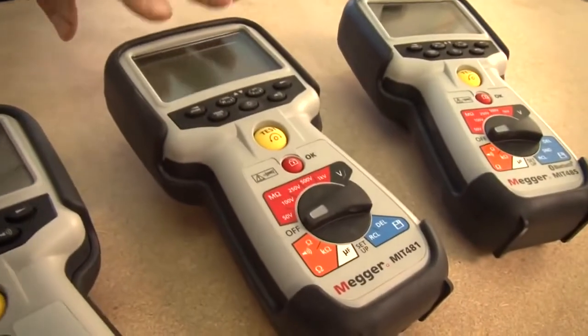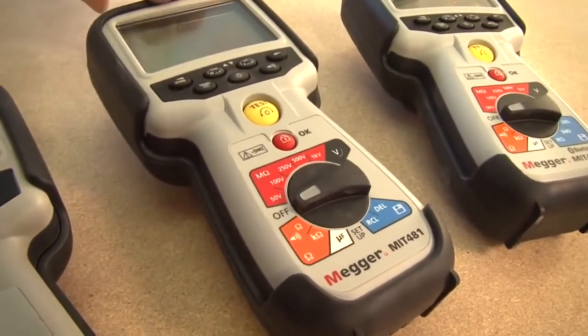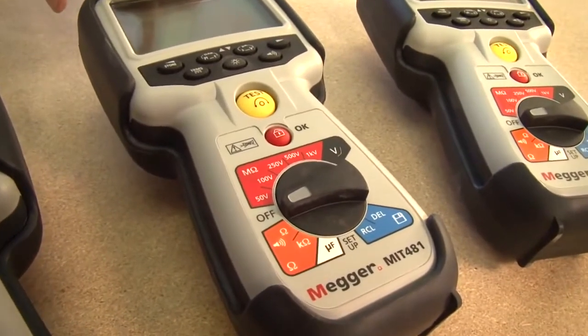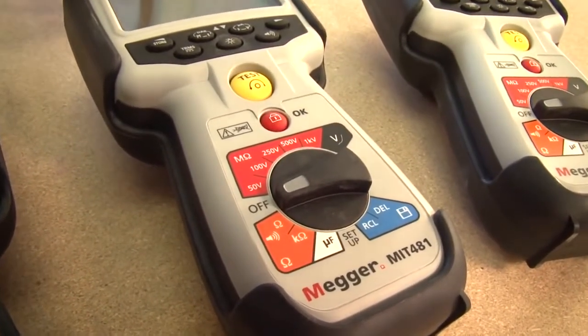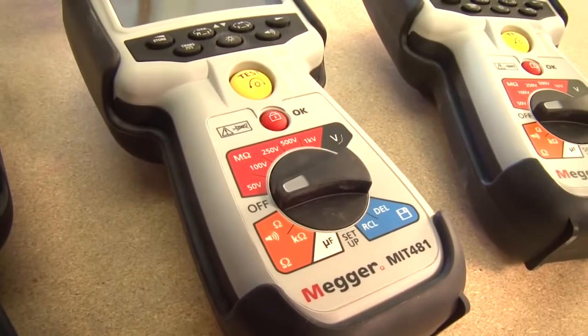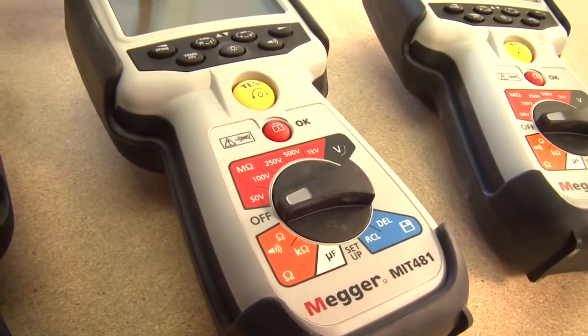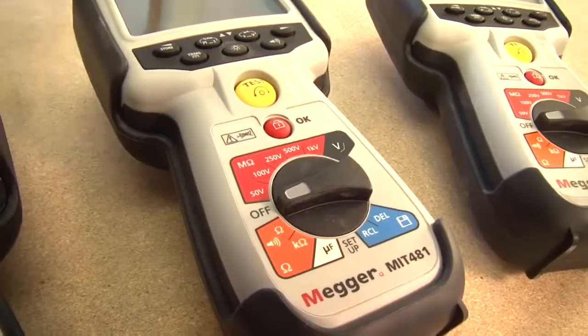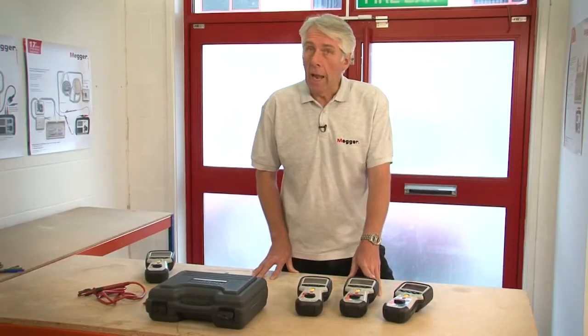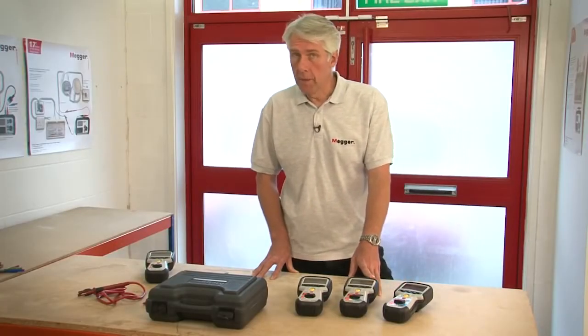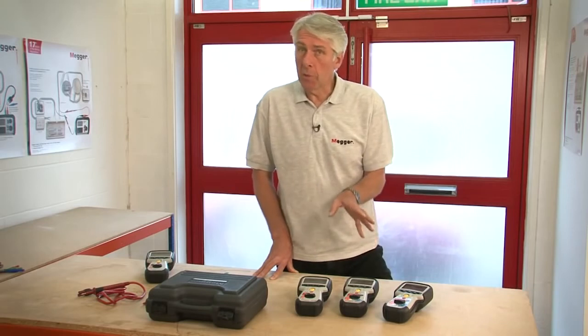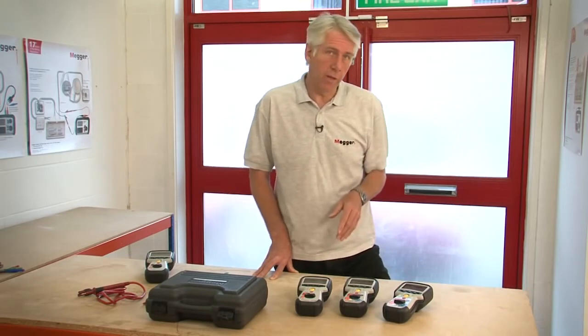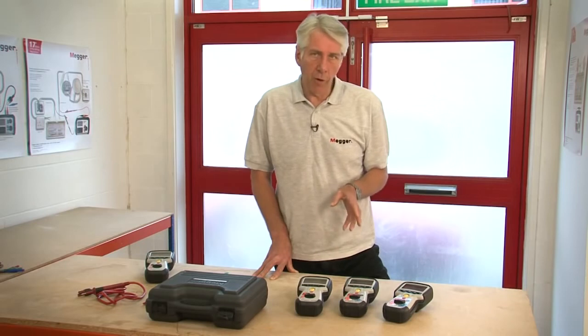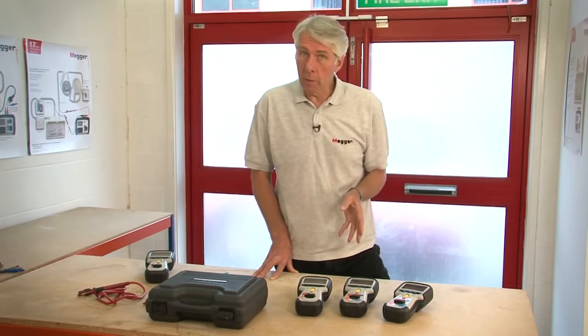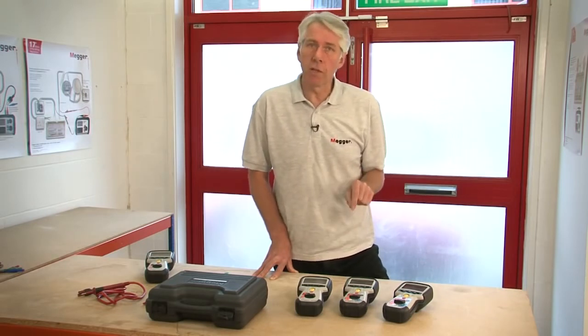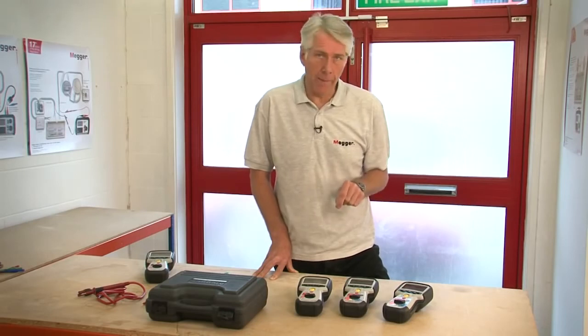Moving up from there, we have the MIT481. This has additional 250, 500 and 1000 volt insulation test ranges, can measure to 200 gigohms and is also able to display leakage current. There's a kilo ohm range and the ability to measure capacitance. Now, using capacitance measurements, it's possible to determine the distance to an open circuit fault. The MIT481 is also able to measure frequency and can store test results and recall them to the instrument display.